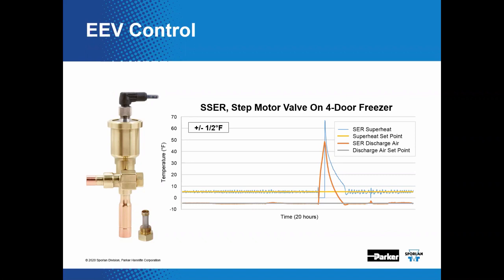Now, here's a log of data that was acquired on a system with a 4-door freezer. The graph displays case temperature in degrees Fahrenheit, discharge air temperature, if you will, as time varies. As you can see, the temperature fluctuates approximately plus or minus a half a degree over time. It tracks fairly consistently with the set point that was established, and it recovers fairly quickly after a defrost cycle. Yep. This is a pretty efficient way to control temperature.